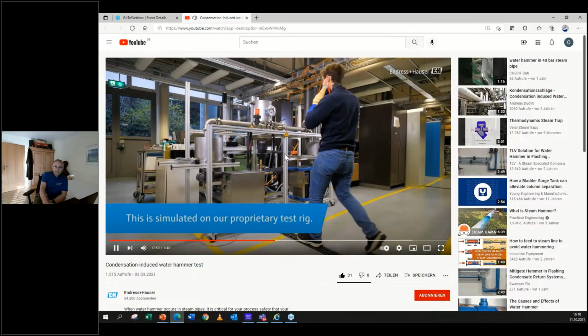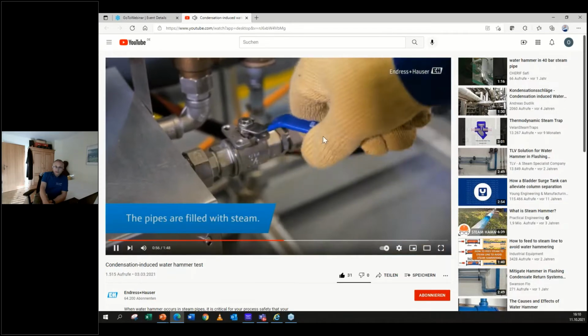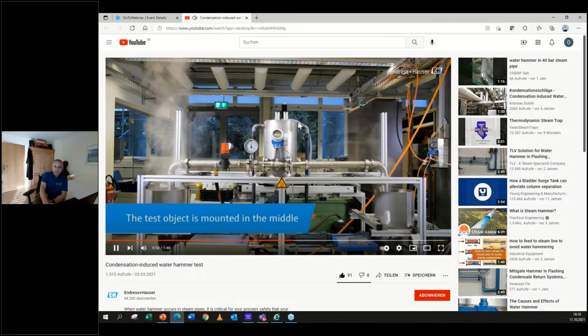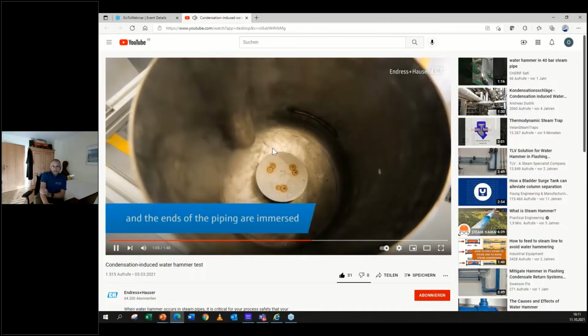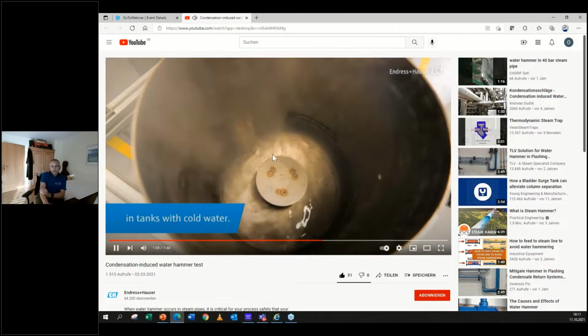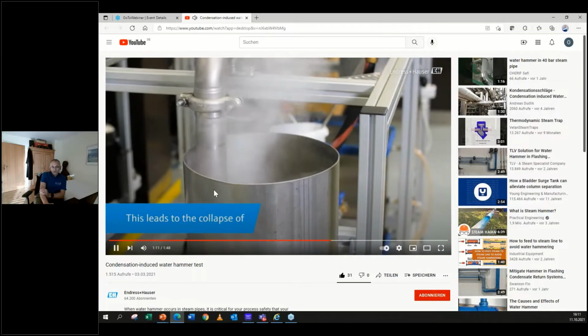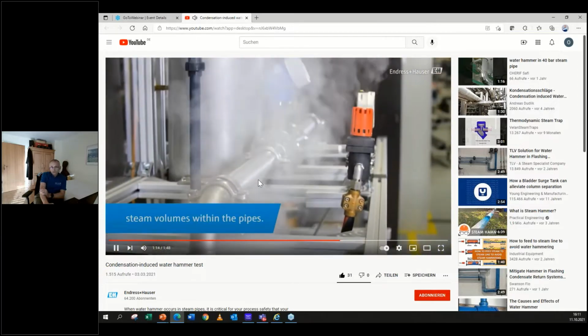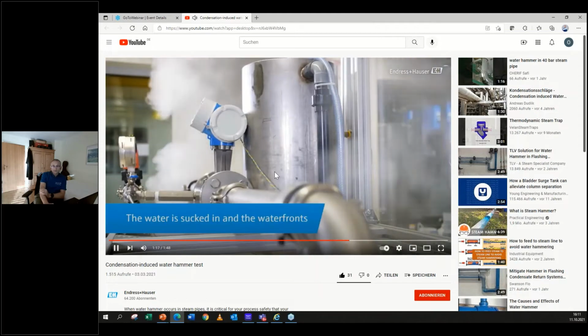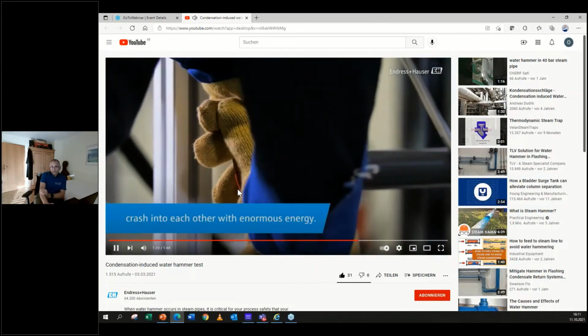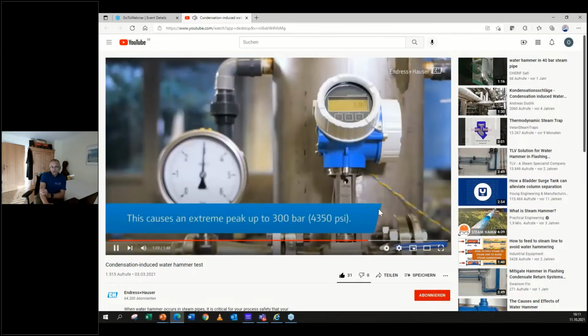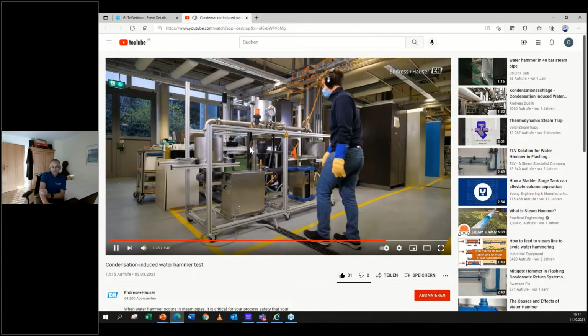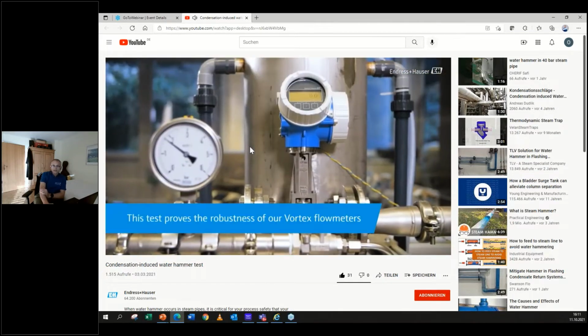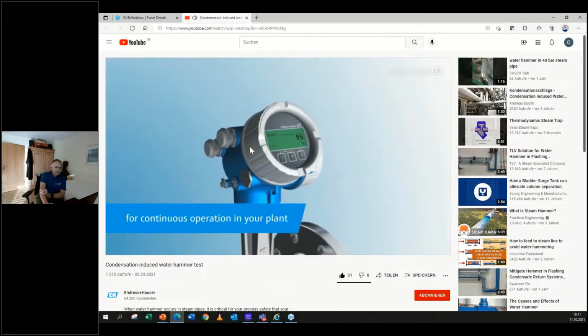And now you see how that test is being done by our R&D. We have a steam generator, we have a steam pressure of 3 bar, which is 45 psi-ish, and we're sending that to 2 sides, and on each side you find a bucket of water. So that steam is going in here, and when we close the steam supply, what's going to happen? All of a sudden we create some vacuum, and we suck the body of water on each side through our device here. And you just see the pressure gauge here showed a small change in pressure. Well, the reality is we got pressure surges of 280 bar.